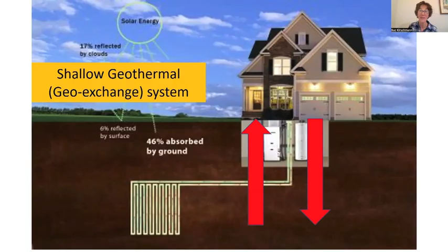In this case, the earth is used as a battery rather than as a heat source. The ground absorbs heat from the sun and stores it year-round at a near constant temperature. In most places on Earth, if you go down 2 to 6 meters below the surface, the ground temperature is a constant 10 to 16 degrees year-round. So shallow geothermal takes advantage of this near constant temperature by extracting heat from the ground and bringing it up into the home during the winter for heating, and in the summer the opposite happens, with the heat being pushed back down into the earth as the house is cooled. Tonight, our guest presenter will explain the ins and outs of how these shallow geothermal systems work.